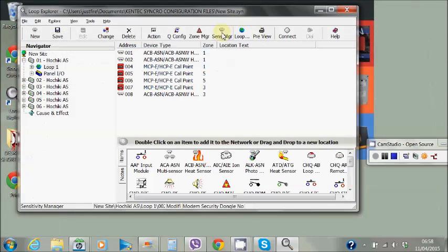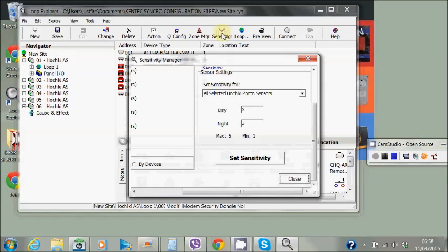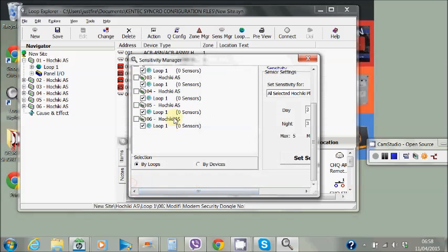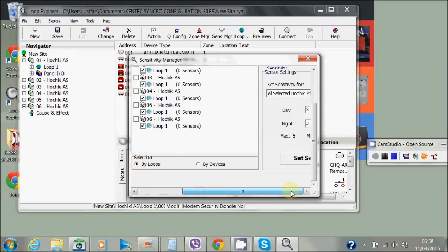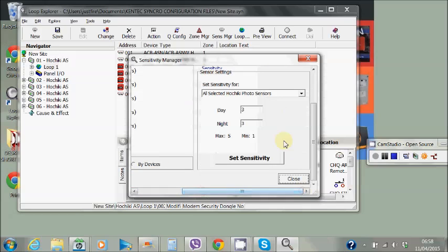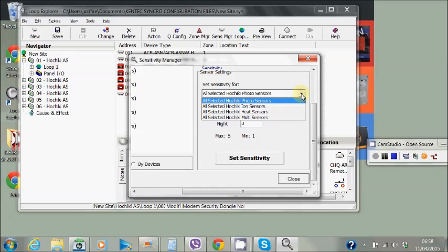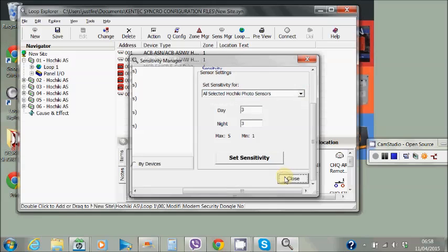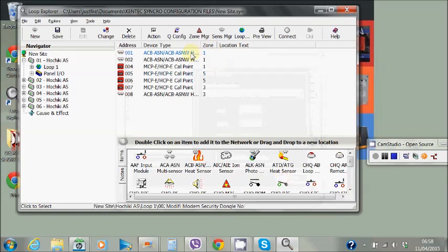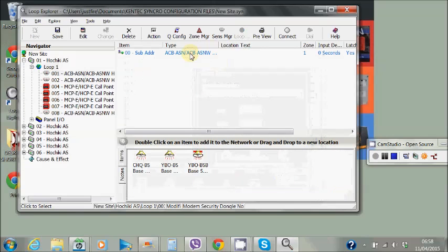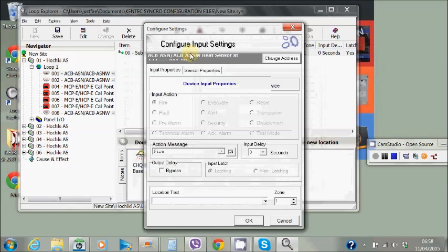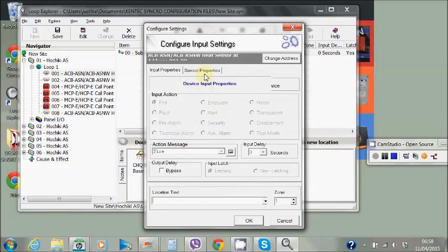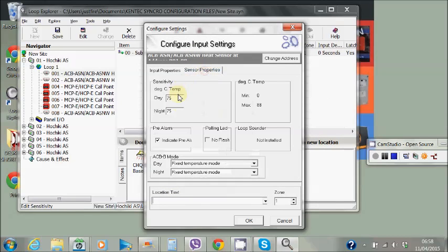The next one is the sensor manager. Again this allows us to very quickly select the loops and panels and nodes across our network. We can do it by loops or devices. And then we can set the sensitivity for them and indeed including the device type. So the heats, the multis, all of this. And then set them across the whole of the loop, the actual loop, rather than individually drilling into each one and changing the sensor properties individually.